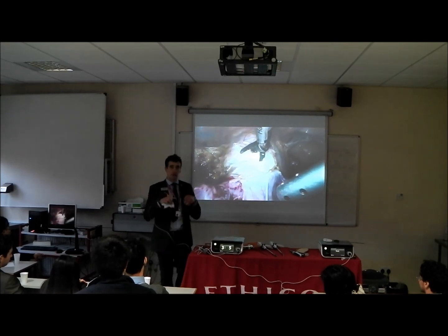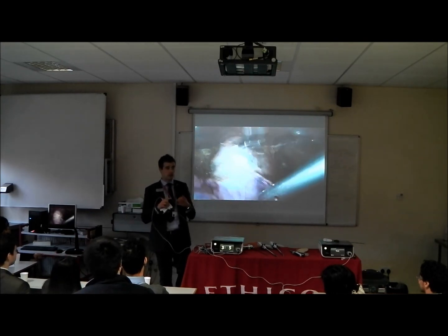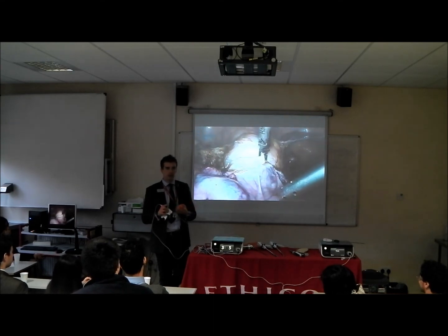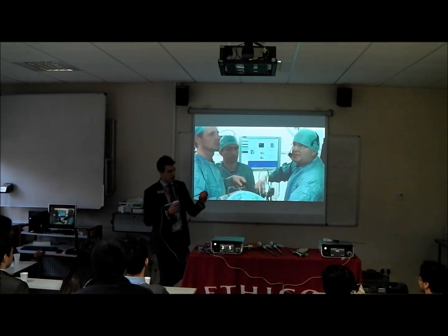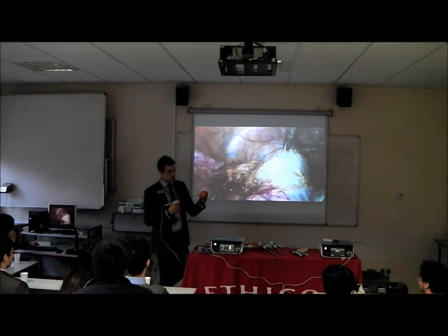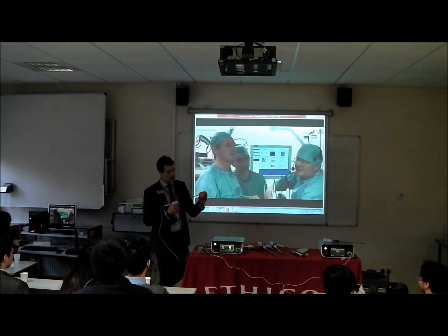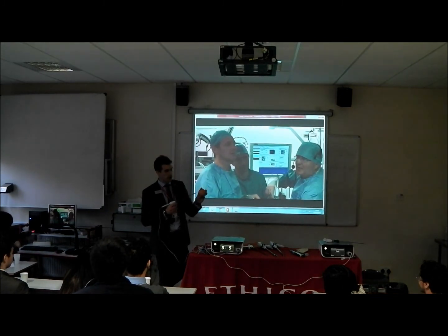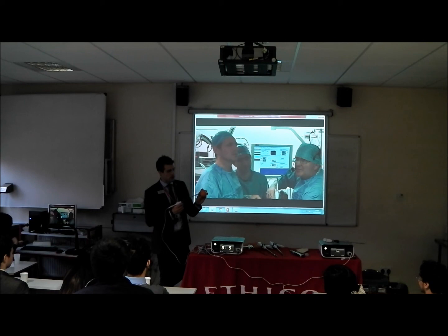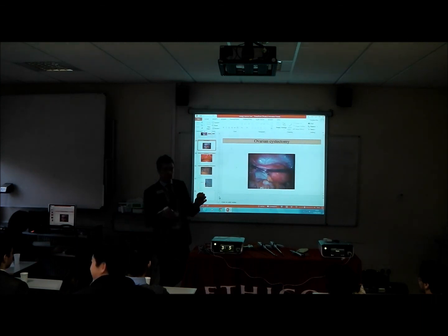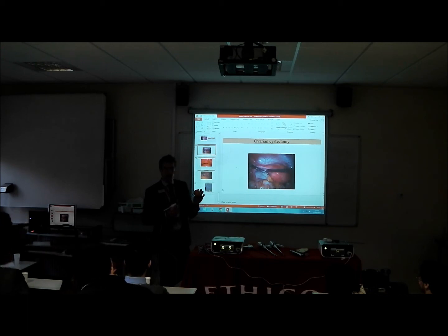When you're cutting, it will cut through quickly, but it will still stop the bleeding. But if it was a vital vessel that you needed to seal, you would coagulate it more. On the orange, if you hold it, you can see that it will cut through, and you can back score all the way down. If you grasp it through, you'll see it will cut through as well. Once you've cut through the tissue and you feel the jaws are together, try not to keep cutting because it will break the device, as it'll just keep rubbing against the top half.